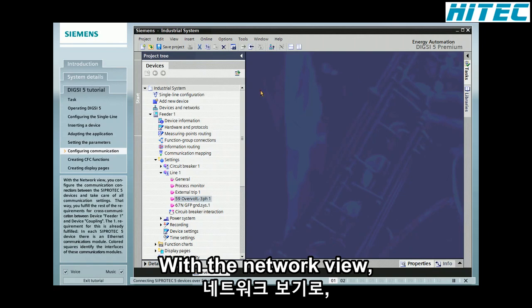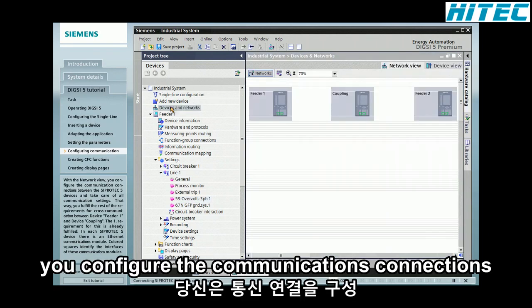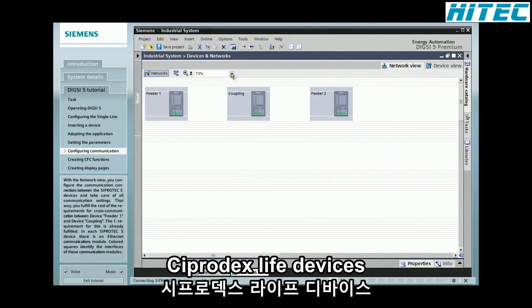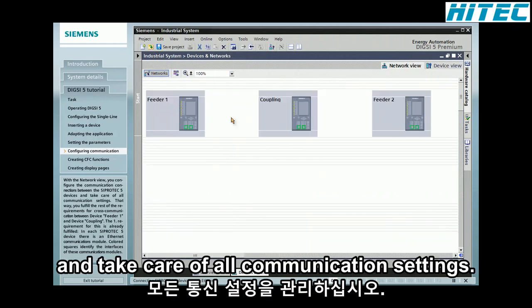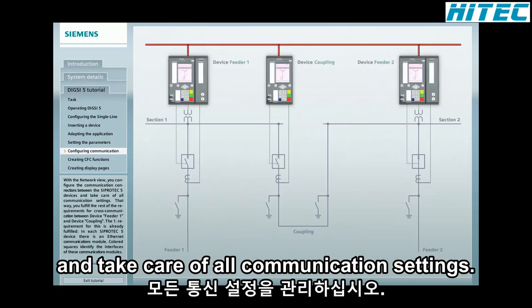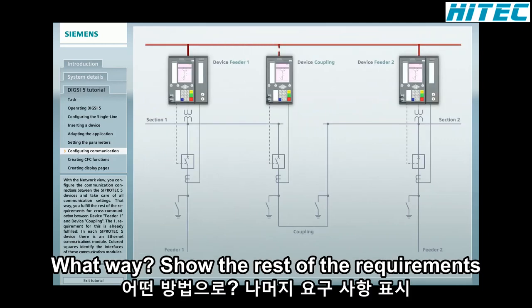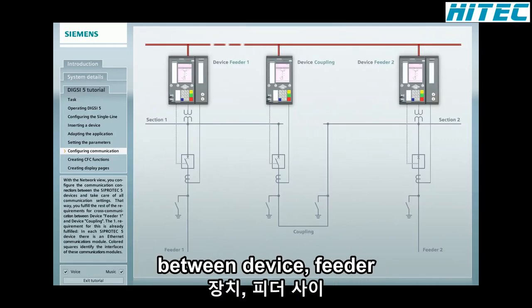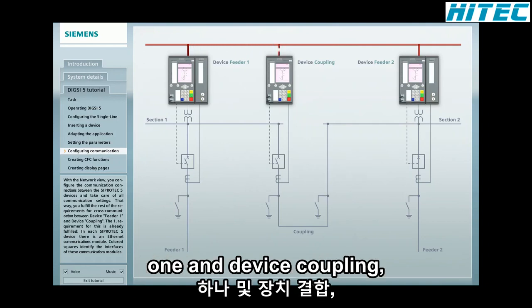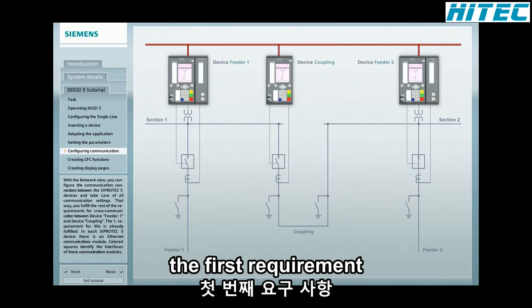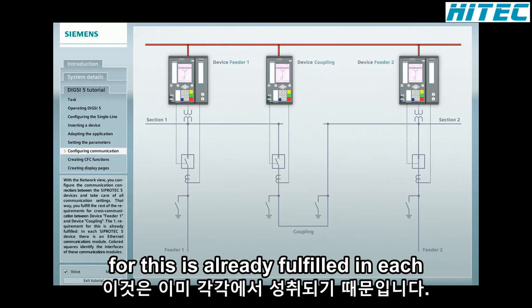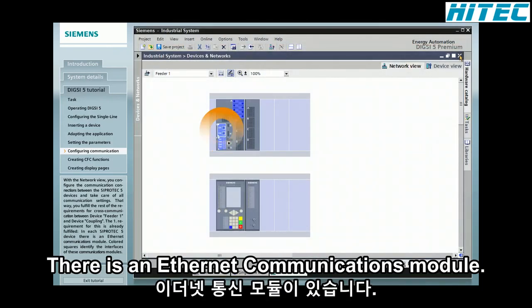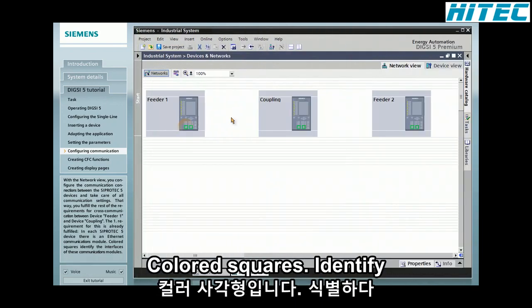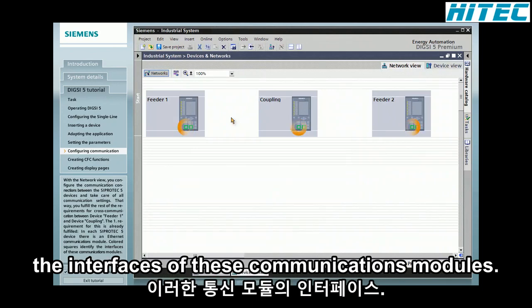With the network view, you configure the communications connections between the SIPROTEC 5 devices and take care of all communication settings. That way, you fulfill the rest of the requirements for cross-communication between device feeder 1 and device coupling. The first requirement for this is already fulfilled. In each SIPROTEC 5 device, there is an Ethernet communications module. Colored squares identify the interfaces of these communications modules.